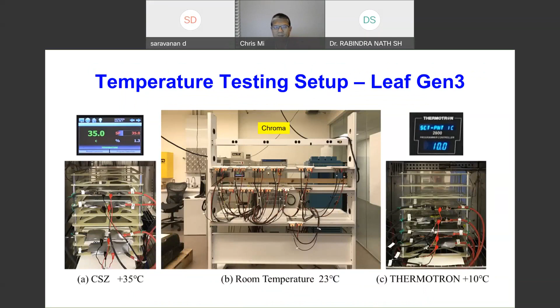The aging test result, in detail, is shown for a few different batteries here. The first one is the Nissan Leaf Gen 1 battery. As you can see from the top, the capacity of the battery cells does degrade. They started around 42 ampere hours, and they degrade all the way to roughly 30 when they reach roughly 4,500 cycles. So this is very linear. So this lasts a long time. The bottom graph shows the internal impedance. As you can see, the internal impedance does increase over time.